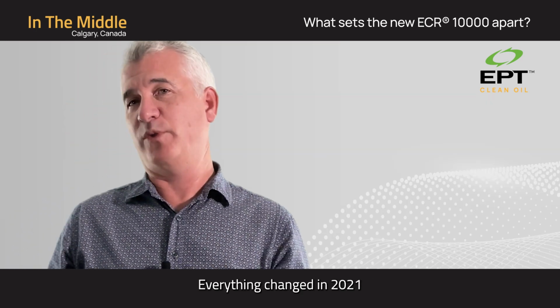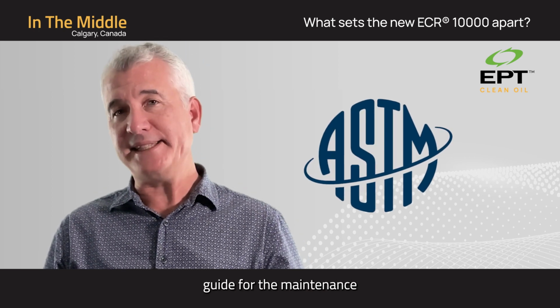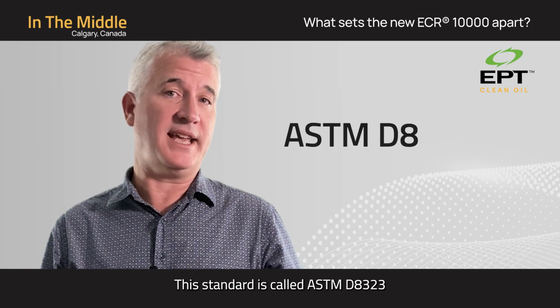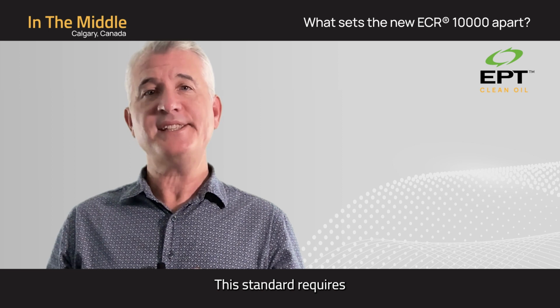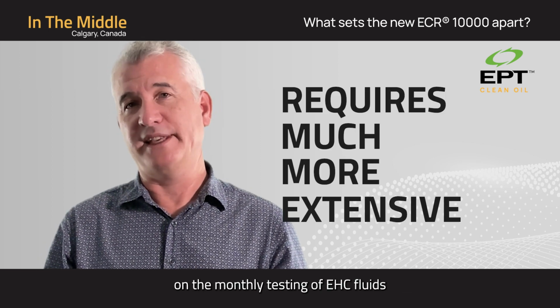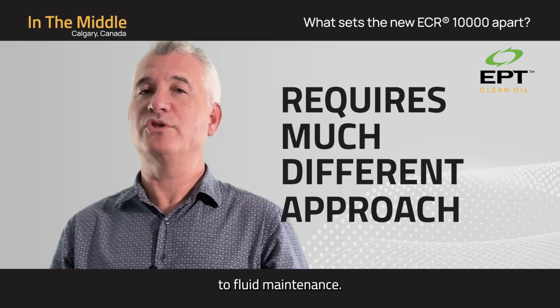Everything changed in 2021 when ASTM came out with the first in-service guide for the maintenance and testing of EHC fluids. This standard is called ASTM D8323. This standard requires a much more extensive test package be done on the monthly testing of EHC fluids, and in turn requires a much different approach to fluid maintenance.